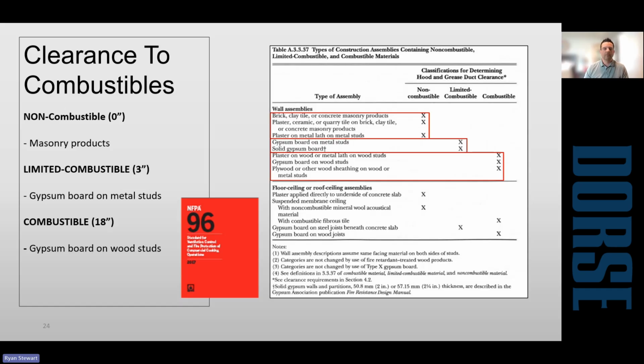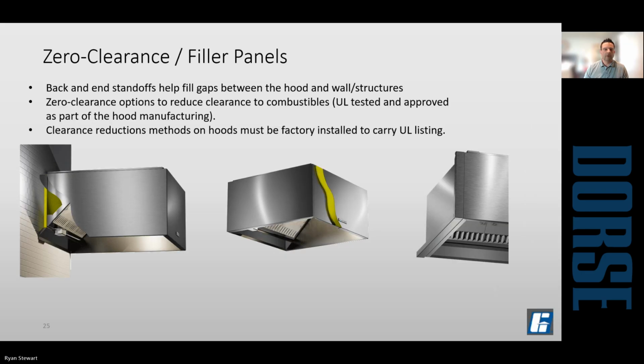So, clearance to combustibles. This is out of NFPA 96. As a manufacturer, if we're aware of surfaces near the hood that are combustible, we can add insulation to the back, top, left, right, front, pretty much any surface. When we do that, the manufacturer's UL listing will indicate that that surface is rated for zero clearance to combustibles.